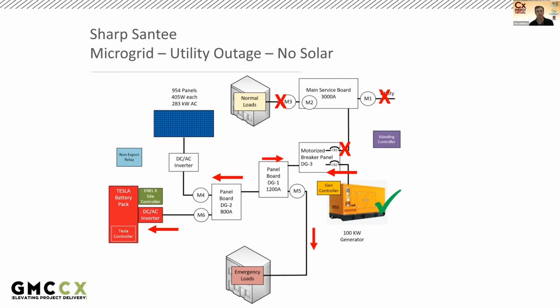Tesla will not give the islanding controller permission to close breaker CB1 while the generator is running. The generator will run for 15 minutes, and then Tesla commands breaker CB2 to open. The generator enters a cool down mode, but it does continue to run. One thing I'll get into a little bit is that Tesla doesn't turn off the generator. It turns it on, but it won't turn it off.